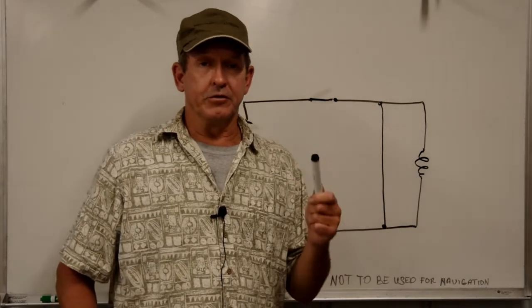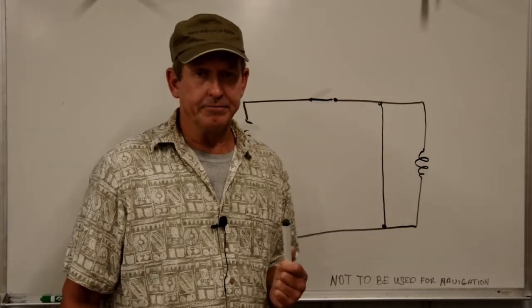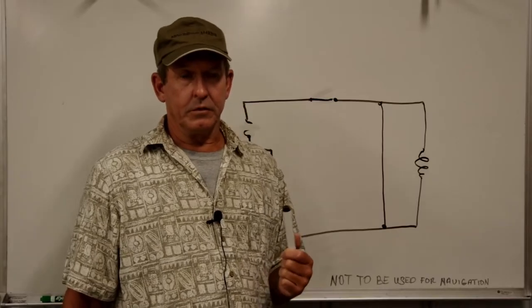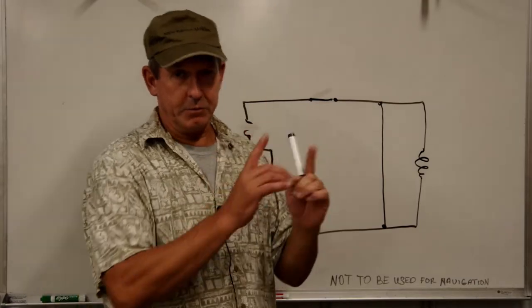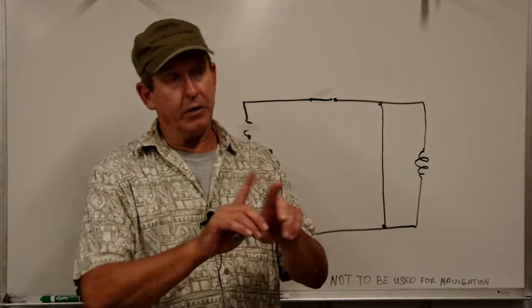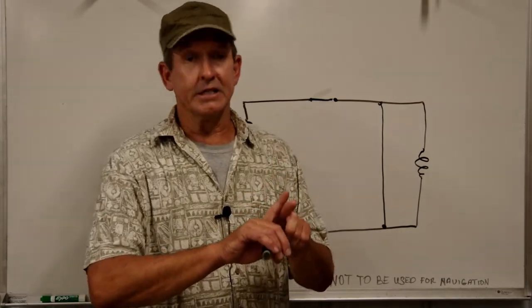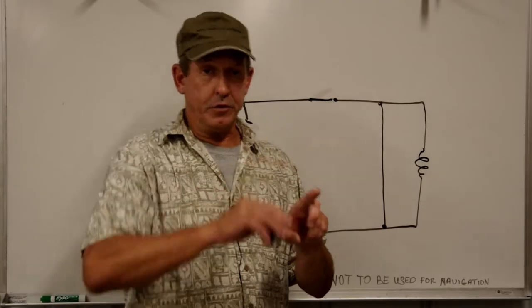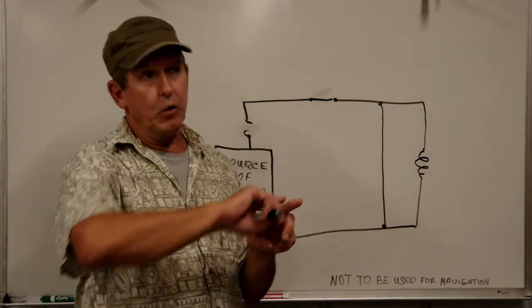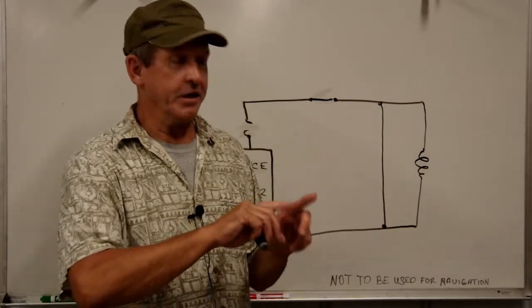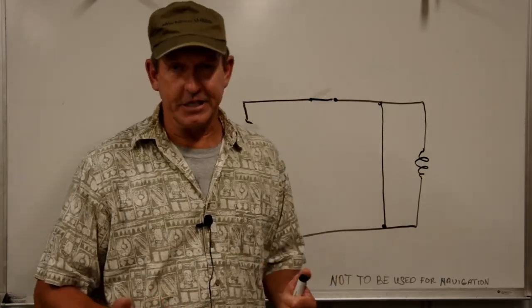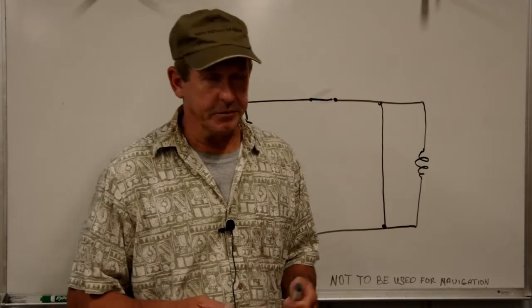I'll put a picture up on the screen of a short circuit so you can see that. What happened with this device is we had two cables coming into it and the insulation had failed — it melted away and the conductors made contact. Instead of going through the device and doing the work we wanted, it found a shorter path through those wires where they touched. Since it was a high resistance connection, it just generated more heat and further caused the insulation to melt away.